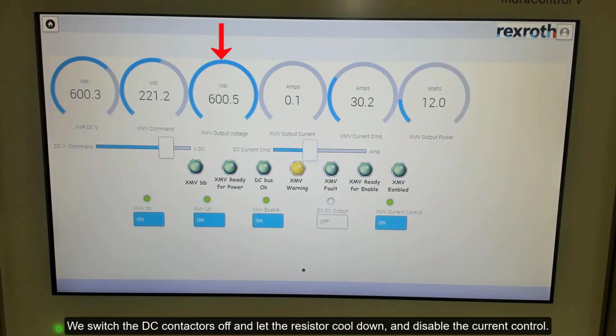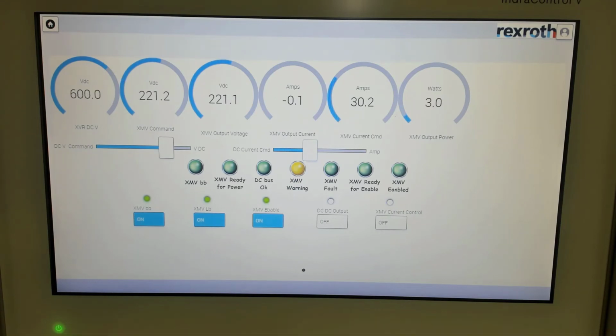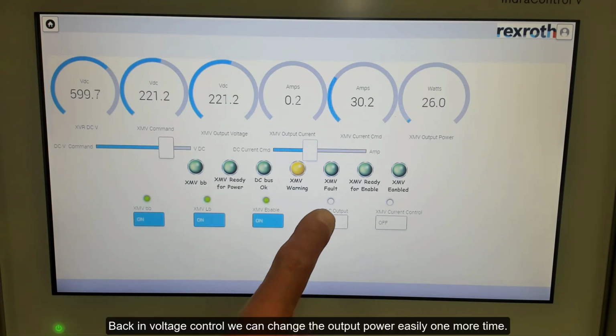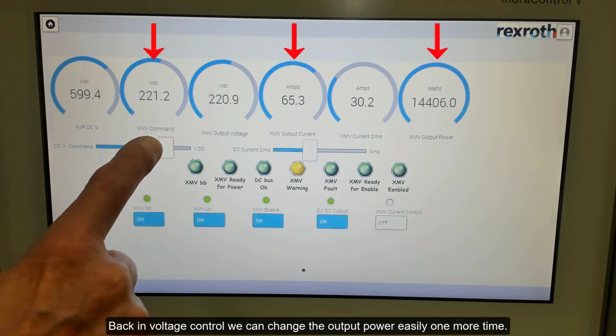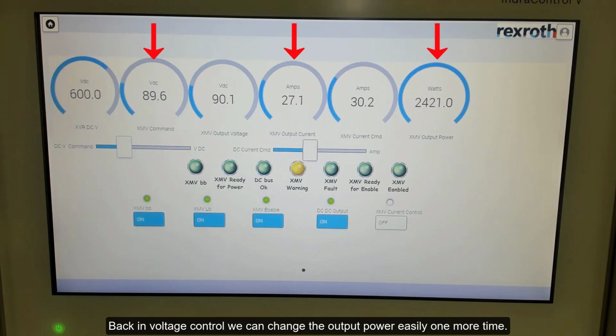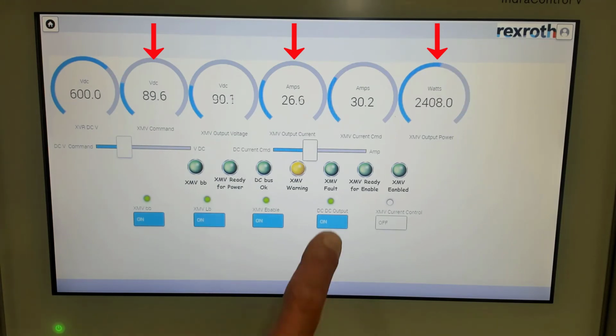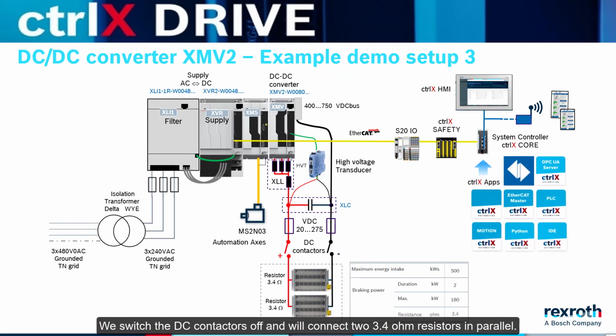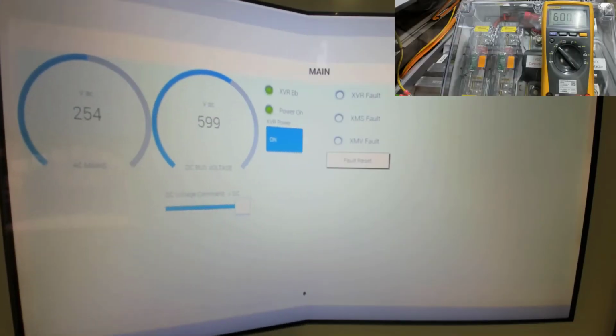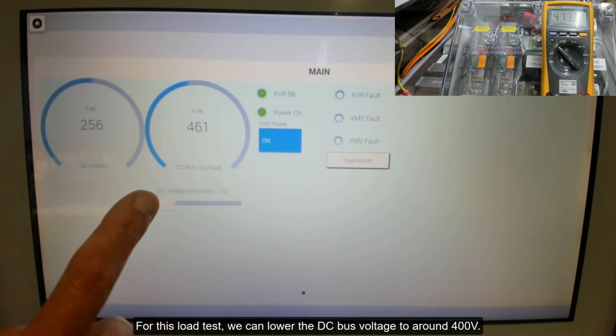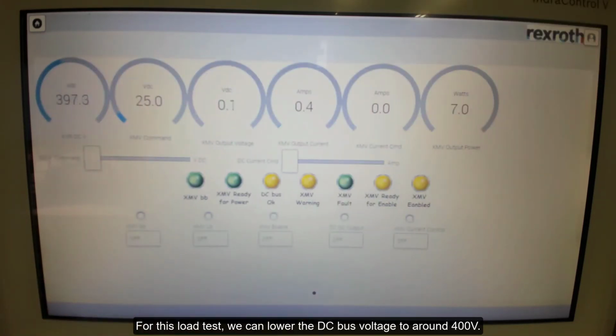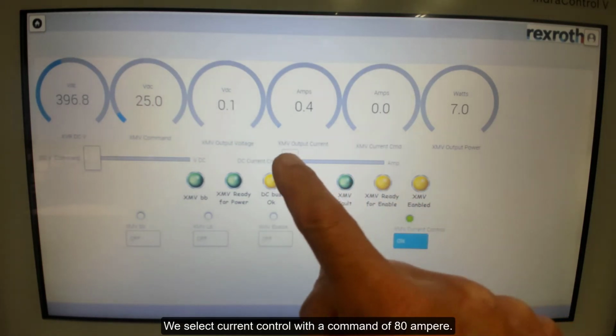We switch the DC contactors off and let the resistor cool down, and disable the current control. Back in voltage control we can change the output power easily one more time. We switch the DC contactors off and will connect two 3.4 ohm resistors in parallel. We could expect that the resulting 1.7 ohm resistor will require at 80 ampere about 136 volt. For this load test, we can lower the DC bus voltage to around 400 volt. We select current control with a command of 80 ampere.